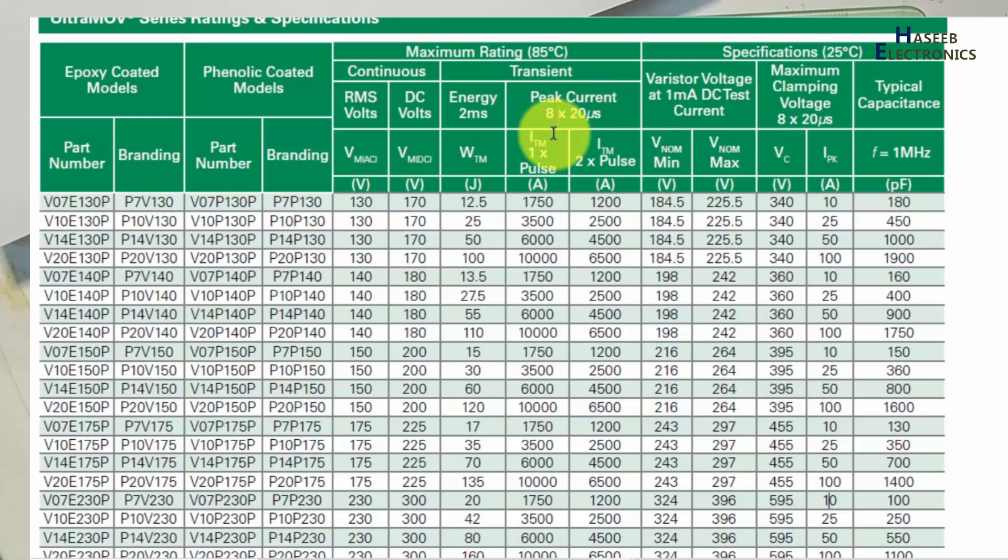If one pulse with this time duration - 8 microseconds for rising up to 90 percent, to 50 percent in the decay - at that time it will allow current 1750 amperes. This one, and if we are discussing this one, it will allow 3500 ampere current. If two pulses, that is 2500. Most of the time it is calculated by multiple pulses.